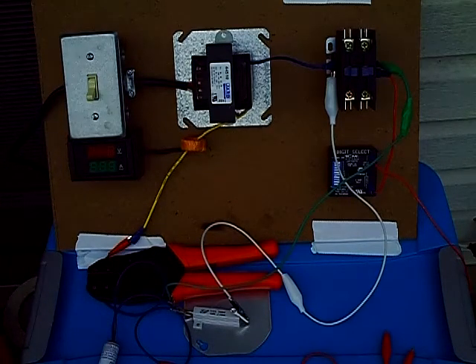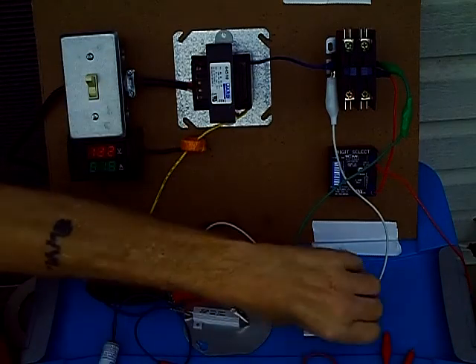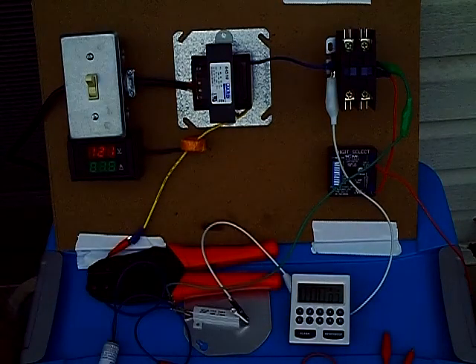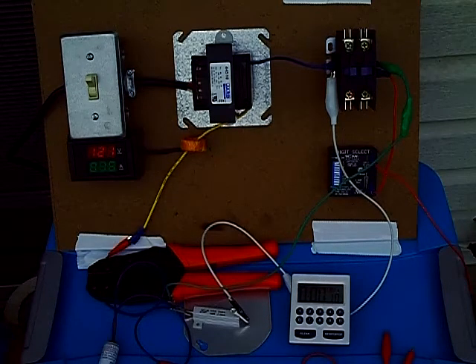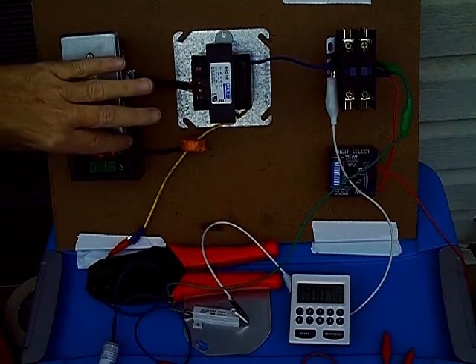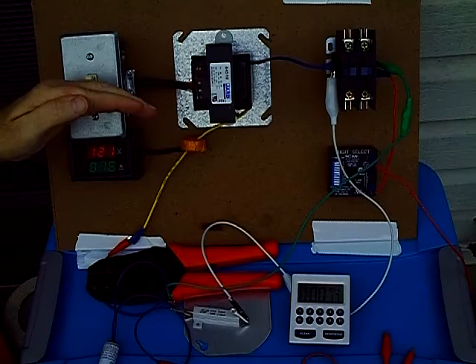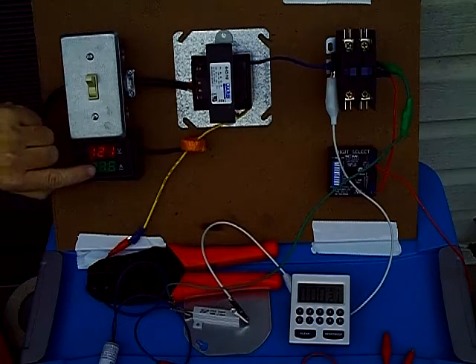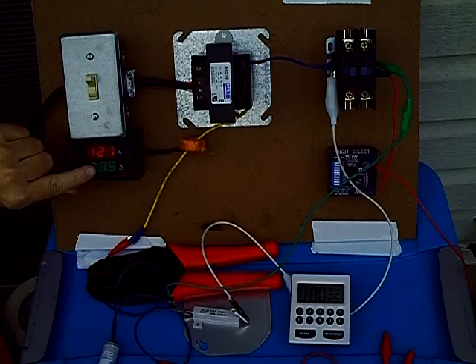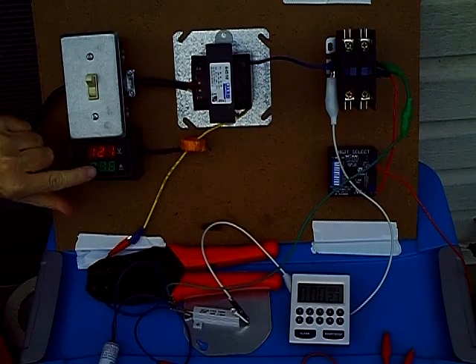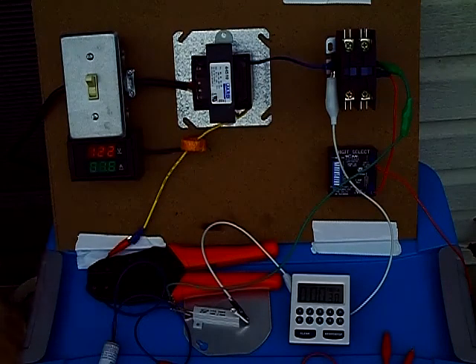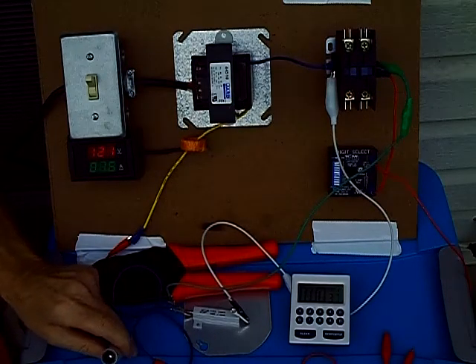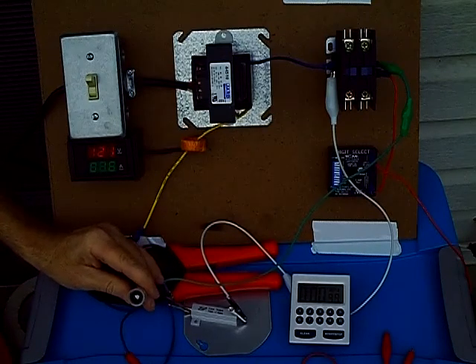Now I've got a timer here I'm going to start and we'll turn this on. If you can see the numbers on the timer, you can keep up with the time and how long it will take to trip the ShortPro tool. Now on this device here, it may be too bright out here, but you've got your primary voltage and it's got 1.6 amps right here going across this meter just to show exactly what it's drawing, to prove that the ShortPro tool can find this.